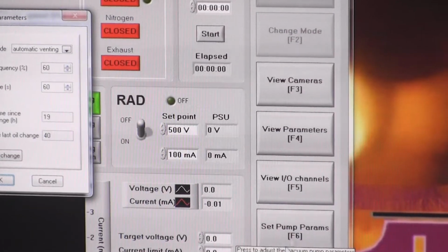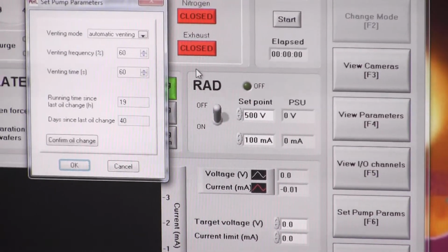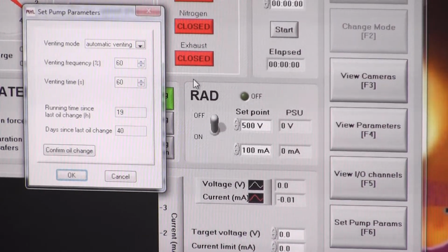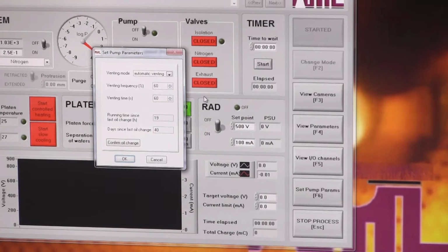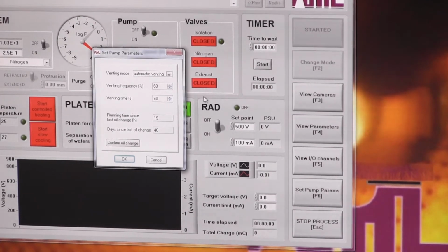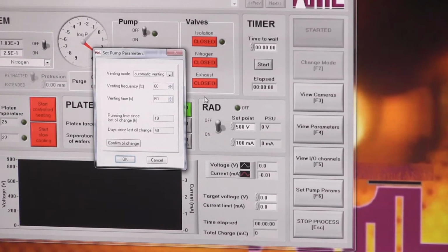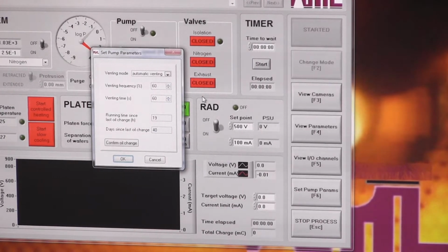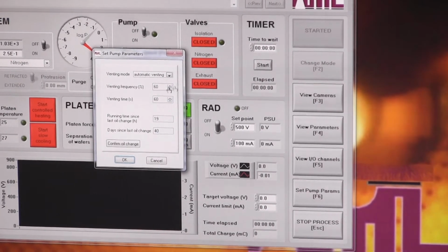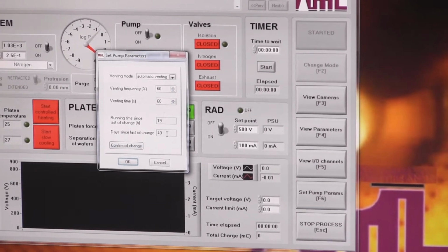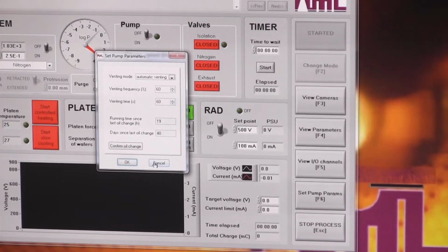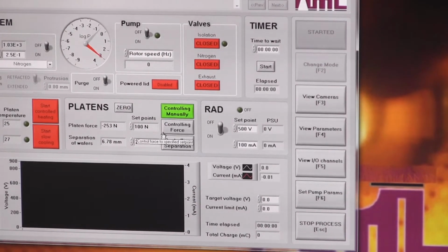Set pump parameters. This is just an excerpt from what you get in the first screen, the process parameter screen. You won't need to change it, save to say that it's done an oil change. So after 2 years, you replace the oil. You can confirm the oil change there. It'll reset these counters back to 0. It'll ask you for a password, and that will be AML.